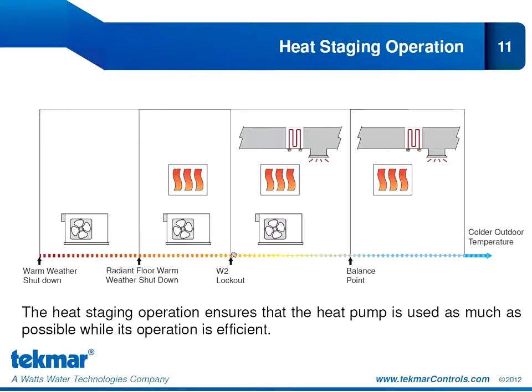If the outdoor temperature continues to drop, we see another new setting, the W2 lockout. And this is similar to radiant floor warm weather shutdown in that it holds off this backup heat. So we're going to prevent it from operating until the outdoor temperature is sufficiently cold that we may actually need a 4th stage of heat. We don't want it coming on before that and overwhelming our system unnecessarily, resulting in high electricity bills. But now it is sufficiently cold. Our radiant floor will be a first stage heat, our heat pump will be a second and third stage of heat, and the electric strip backup can provide a 4th stage of heat.